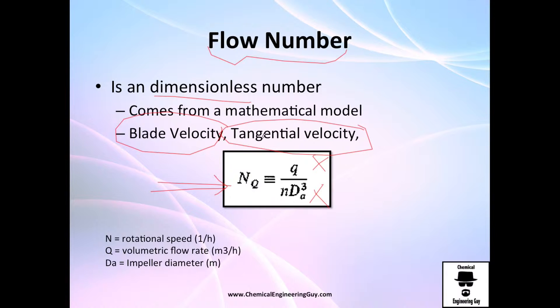Here goes the formula. You've got the flow number is equivalent to that of the volumetric flow rate divided by the rotational speed and the impeller diameter to the third power.